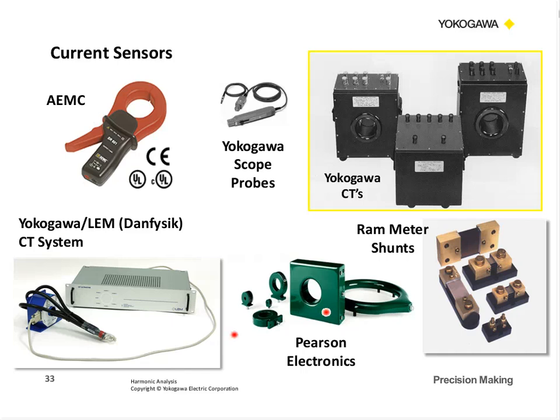And then this is a system that we developed with Yokogawa and LEM. Used to be Danfysik. Maybe some of you are familiar with that. This is a very specialized DC to high frequency current transformer. It is an active type, so it has a power supply signal conditioning unit with it. And these will go up into the hundreds of kilohertz and very accurately make current measurements, like 0.05 to 0.02% of full scale. So it's another good solution for your current measurements.